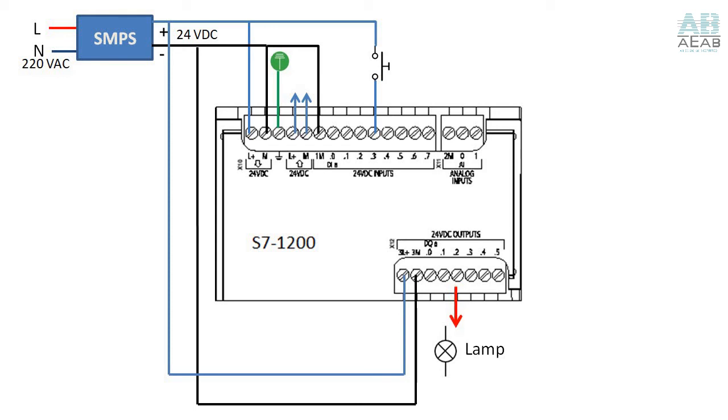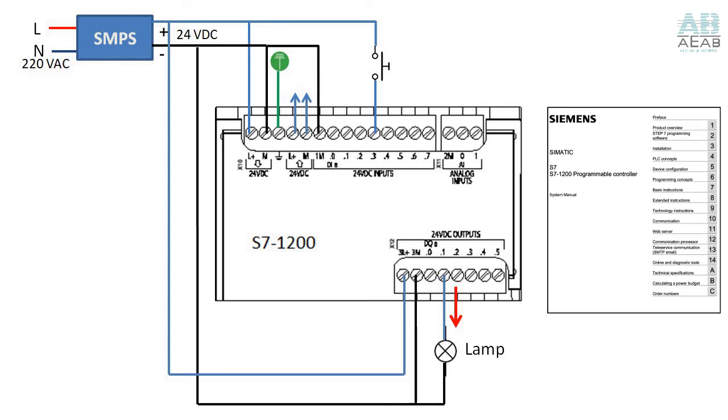So we have to connect one terminal of the lamp to the output terminal of the PLC and the other terminal to negative of the 24 volt DC power supply. In this way, our indication lamp will glow as it gets connected to both positive and negative polarities when the PLC output pin is high as per the program execution. Most PLCs follow the same wiring methodology. You need to read each pin's specification printed nearby carefully, or you can take help from the PLC documentation.